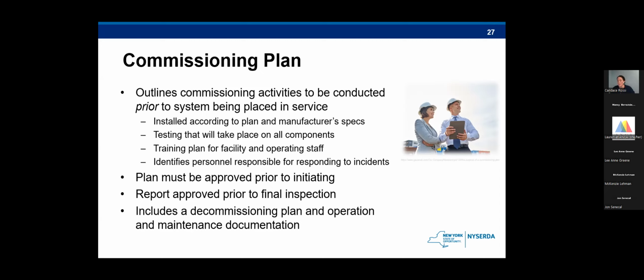Basically, all of this needs to be approved by the fire code official prior to the start of commissioning. It also requires a commissioning report describing the results of the commissioning to be provided to the code official before the final inspection and approval. So there is a lot of information up front that the applicants are required to provide to the town to show that their project is installed safely and has met all these requirements prior to going into operation.